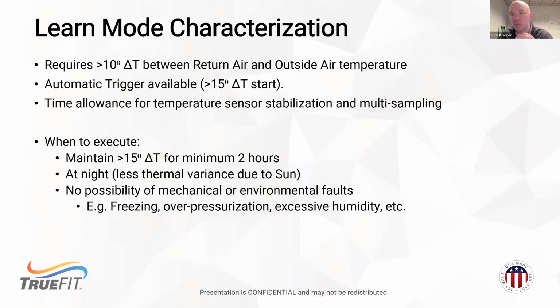It depends a little bit on the speed of your actuators. But this is something that would generally run in the evening or at a period where we can stroke that damper from min to max to profile the entire performance of that damper assembly.